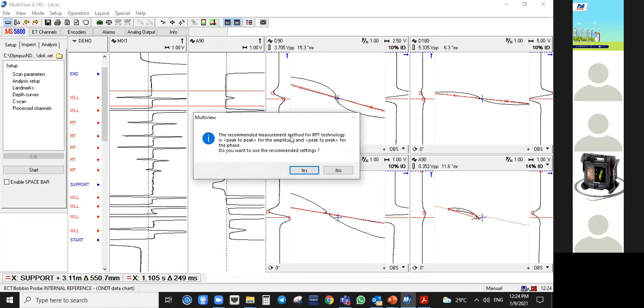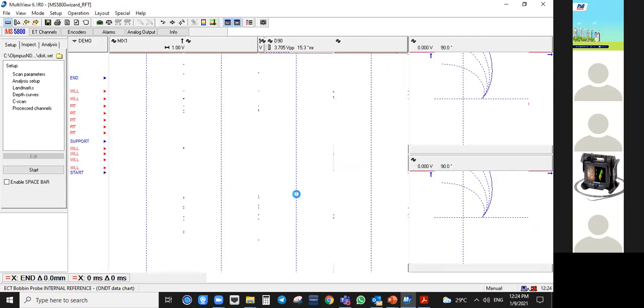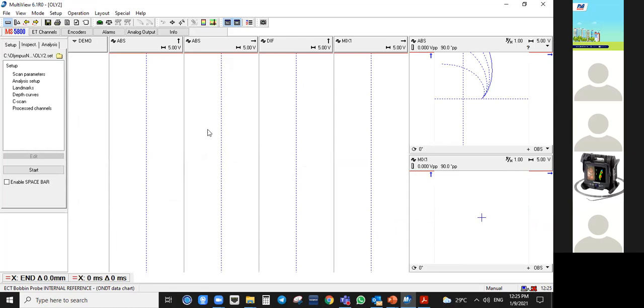Here, the recommended measurement method for the RFT technique is peak to peak. For ECT it is maximum rate, MR, but for RFT it is peak to peak. Just press yes when asked if you want to use the recommended settings, and it will automatically change your configuration. So you have 4 strip charts and 2 voltage planes. The difference is that for ECT you use the impedance plane, while for RFT you use the voltage plane.